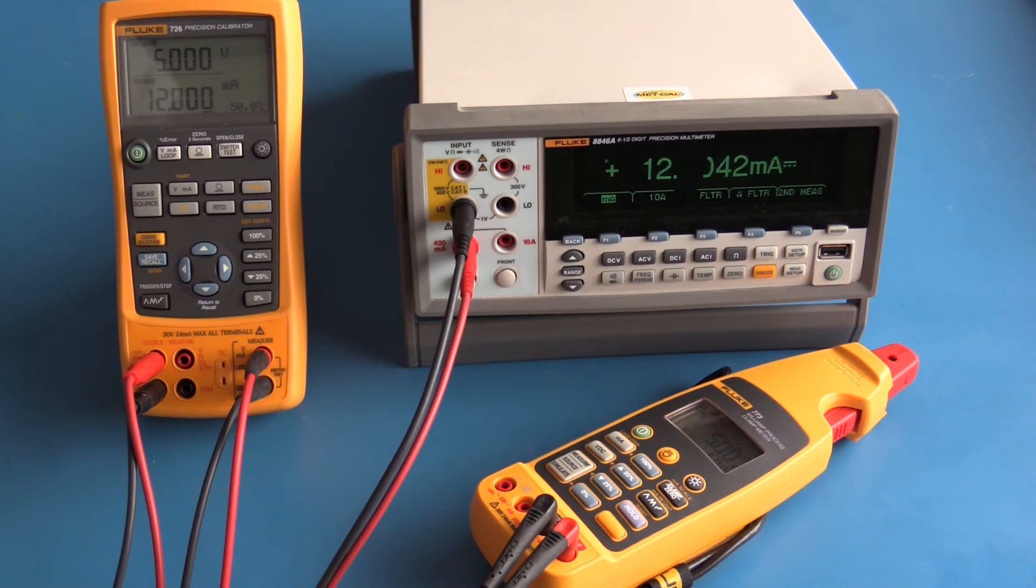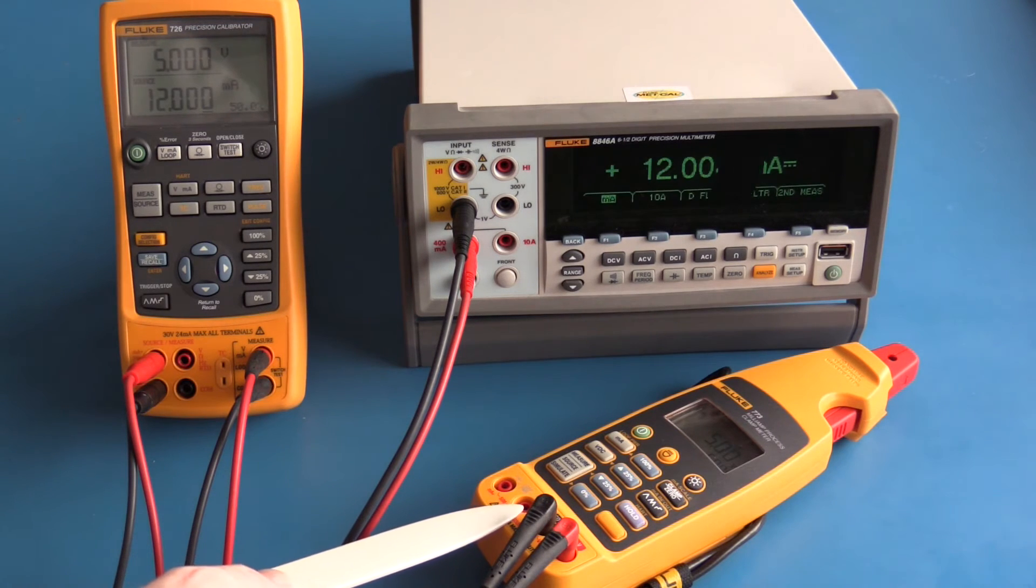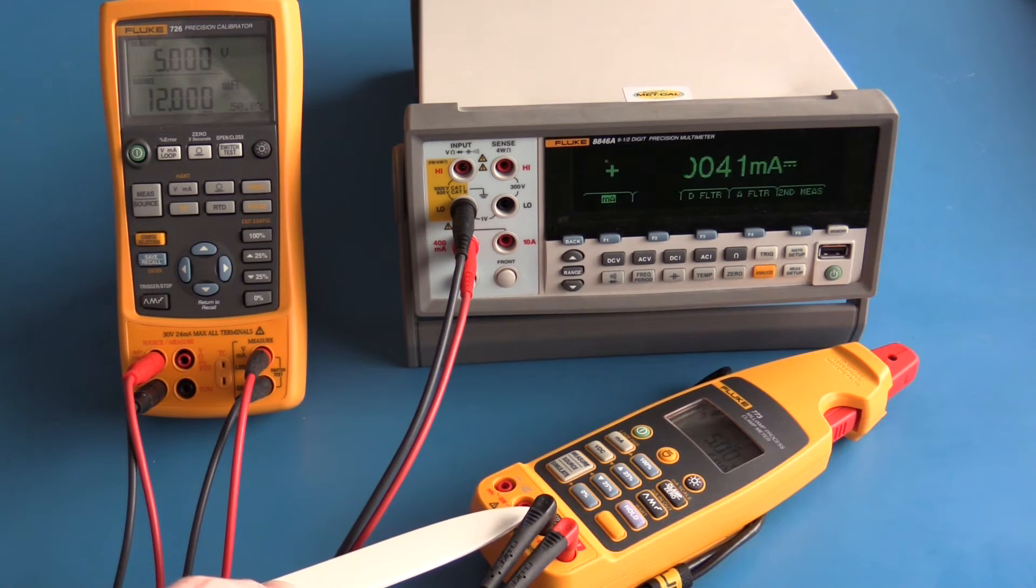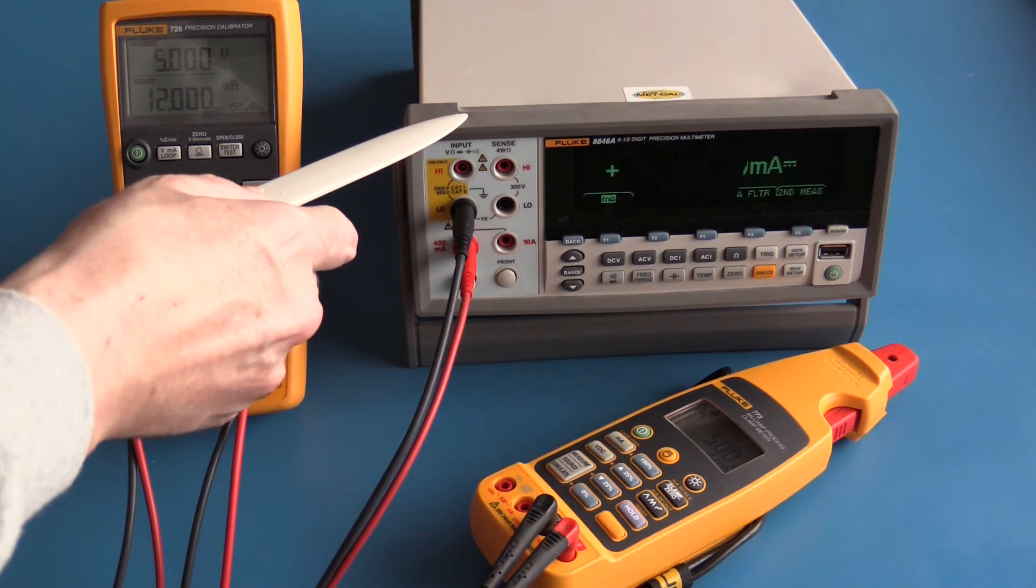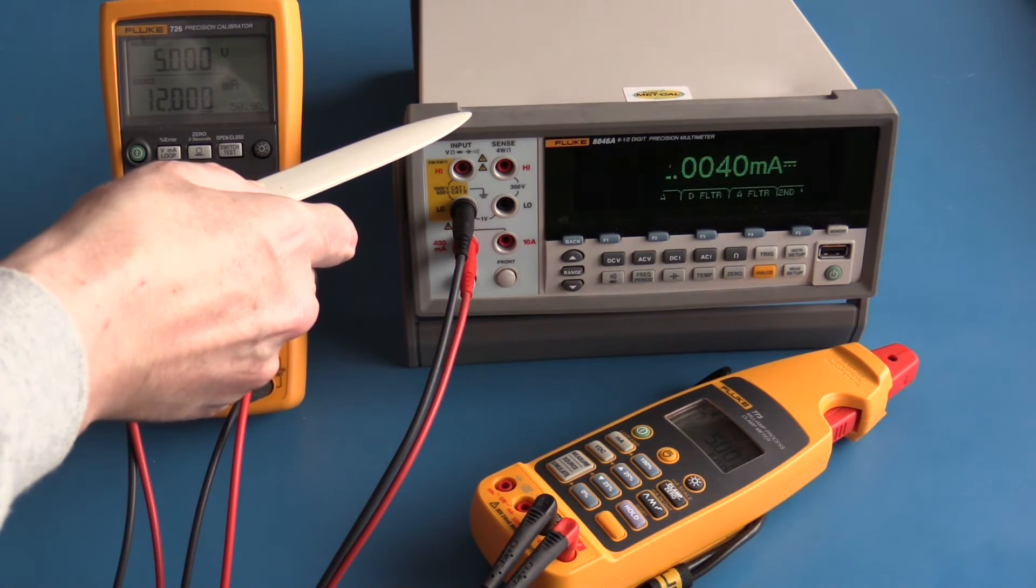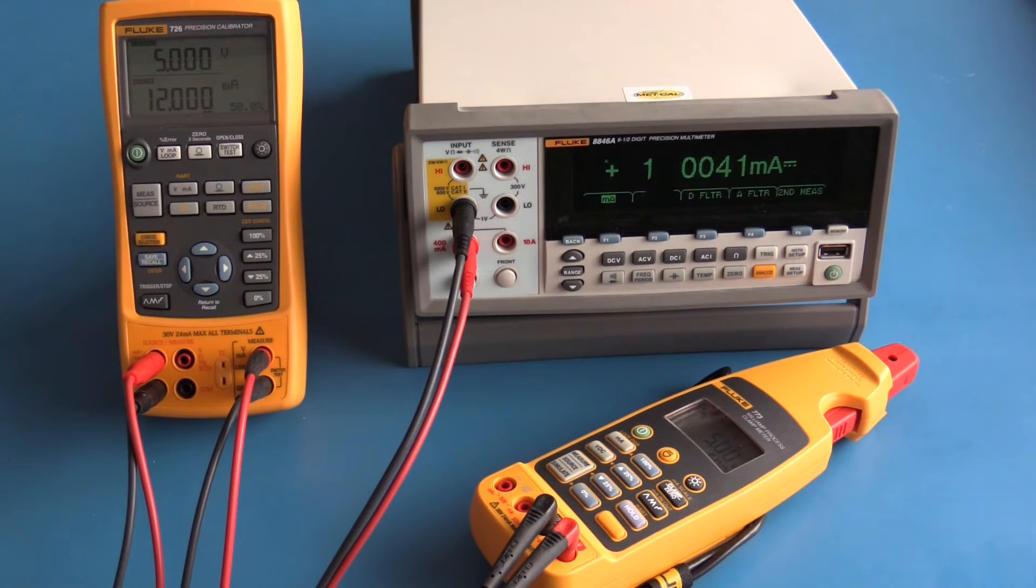The Fluke 726 is now set up to measure voltage and it will source 12 milliamps. The Fluke 773 is set up to source 5 volts which is being measured by the Fluke 726, and the Fluke 8846a is showing approximately 12 milliamps which is what the Fluke 726 is set up to source.